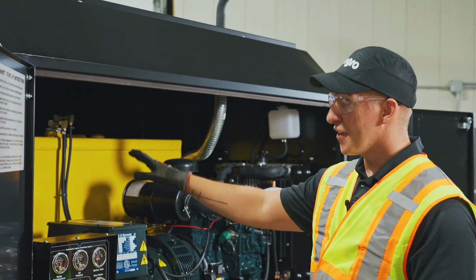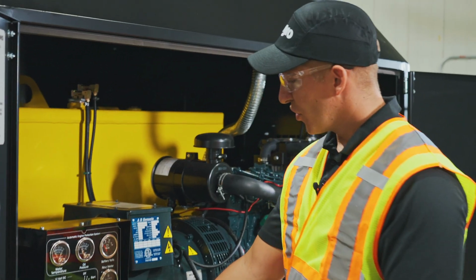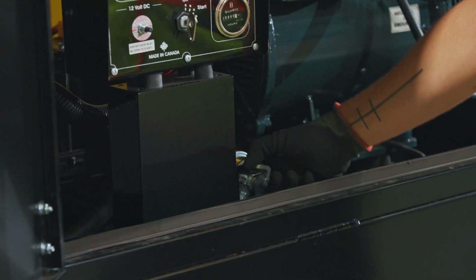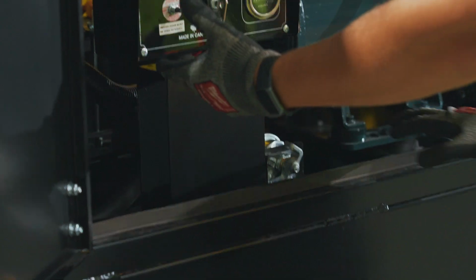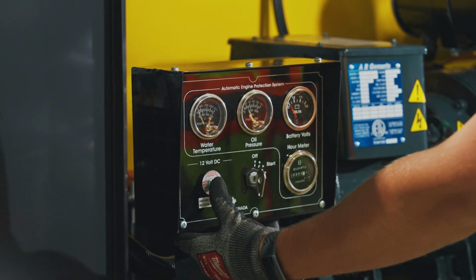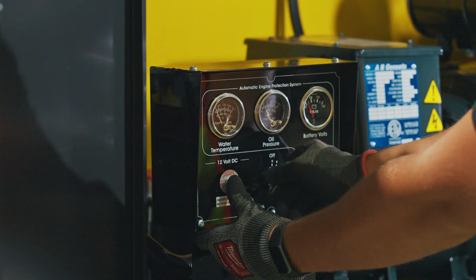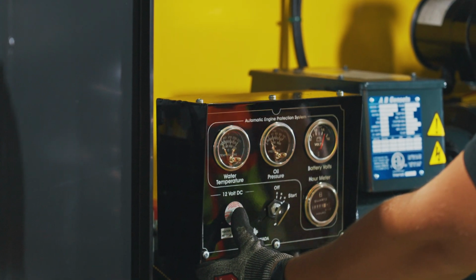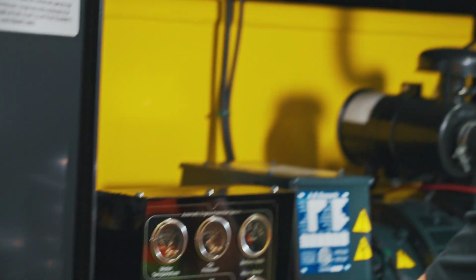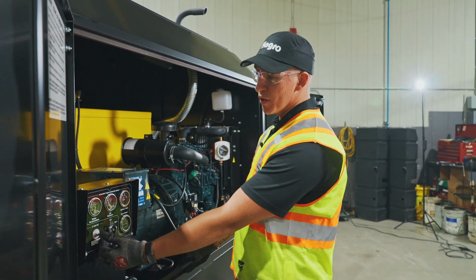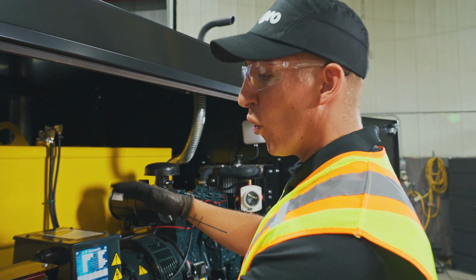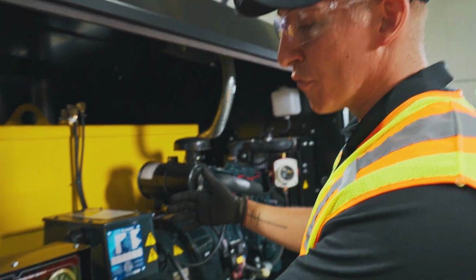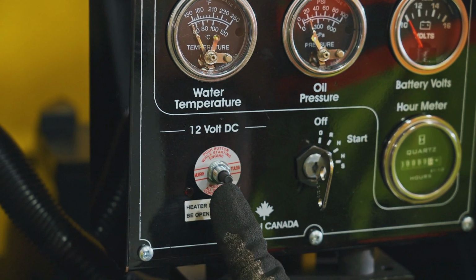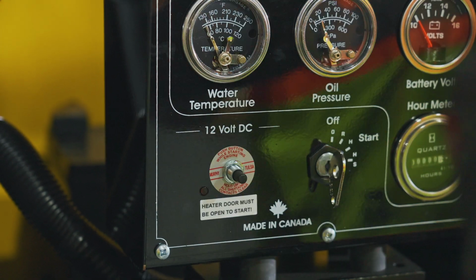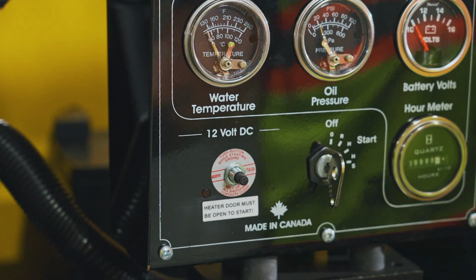With the heaters in the off position, that won't start your heaters at this point. You're going to open your battery lockout here. Now that's unlocked. Press down your ignition button and then turn the key, and it will turn it over. So when you're starting the genset, you will need to hold that ignition button down the whole duration of startup until it turns over. Because we're inside, I don't want to leave this trailer running for too long, but you will have to have your thumb remain on that until it's had a few seconds to warm up, and you should be able to release and everything will stay running.